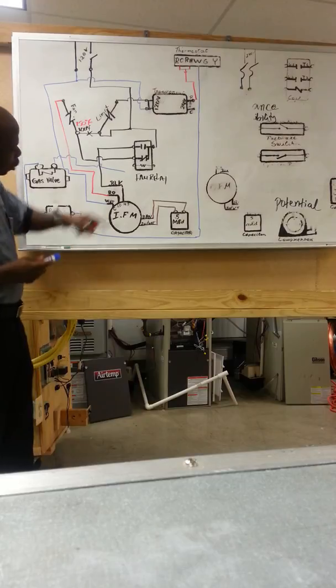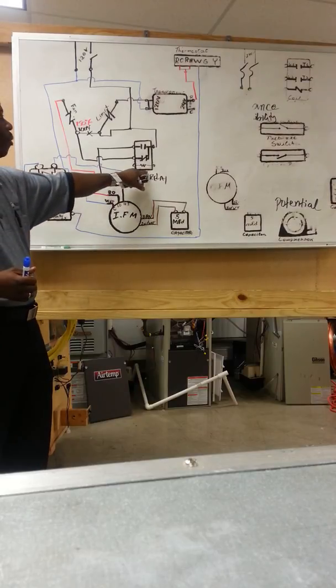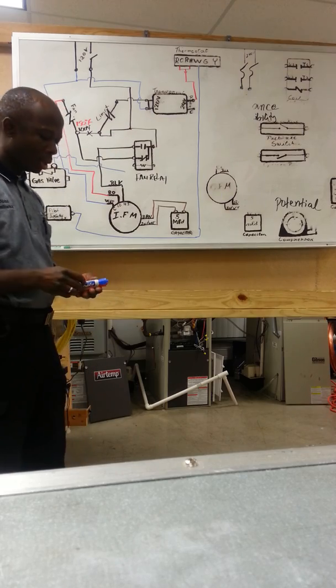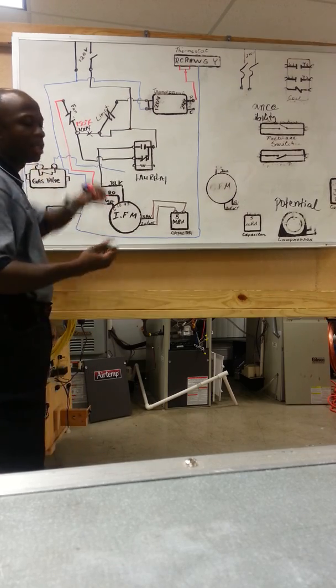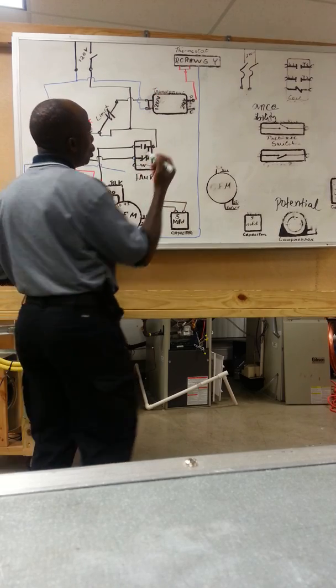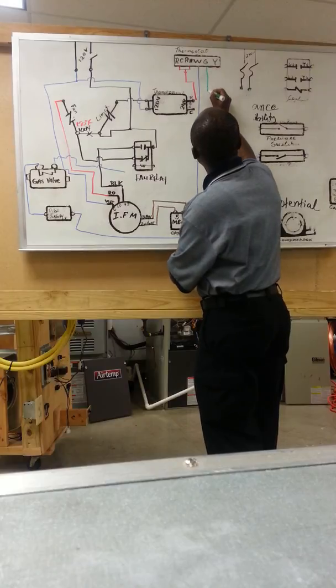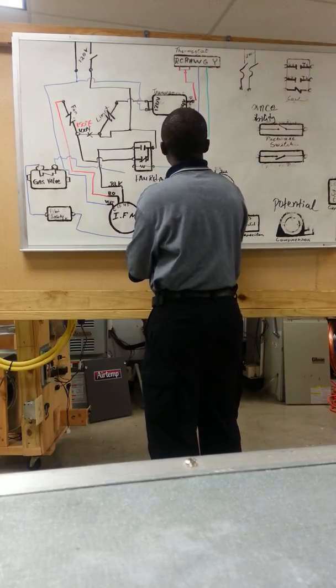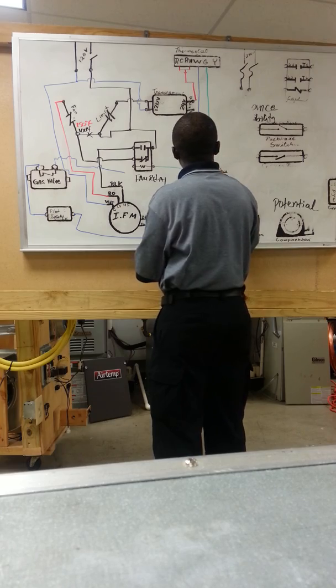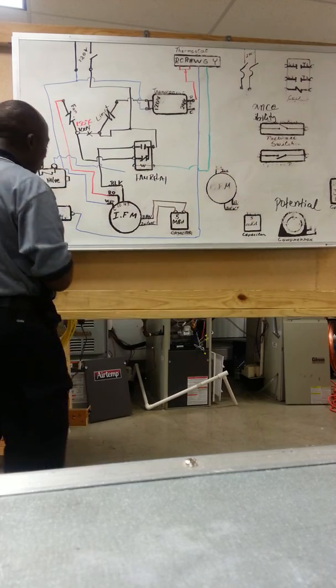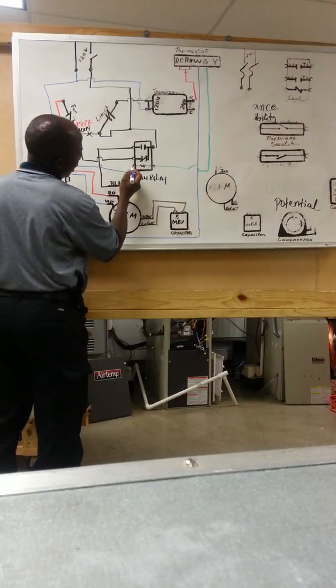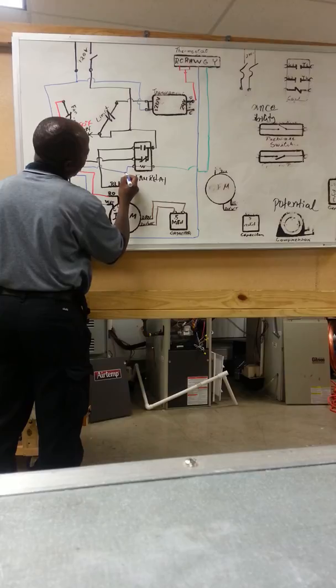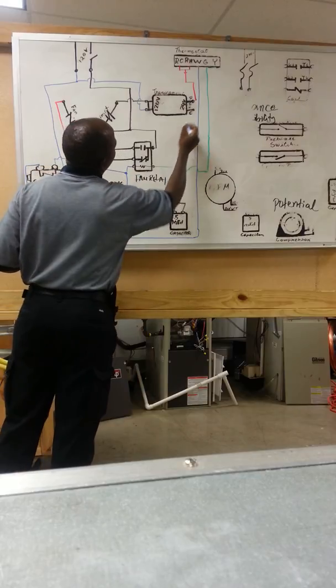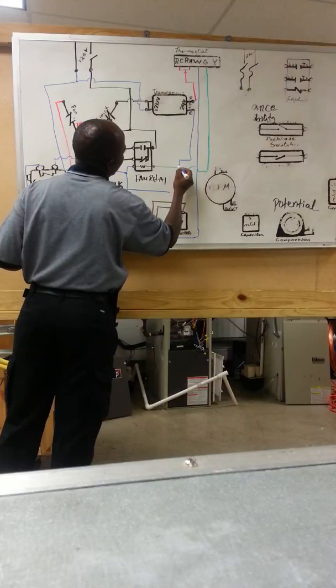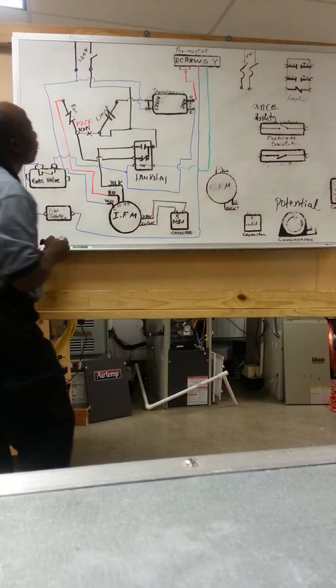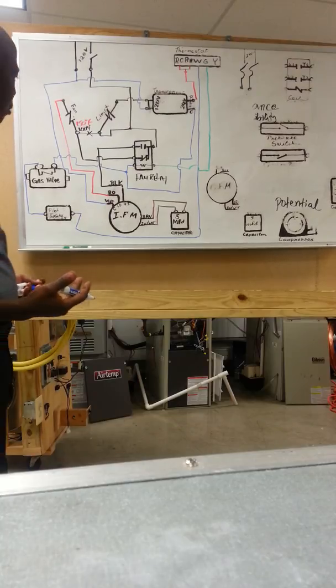But why I'm going to hold it here for a minute is I'm going to need 24 volts here also, common going to the transformer common. So in that case, I can jump them together, pigtail them, and send them back to the transformer. So the G, which is the fan relay from here, this G is going to come down, and it will get into the fan relay 24 volts. And then from the fan relay, 24 volts is going to get out from here. Now I can pigtail these two together and take one wire, bring it over to the transformer common. So pretty much the heating circuit is done.